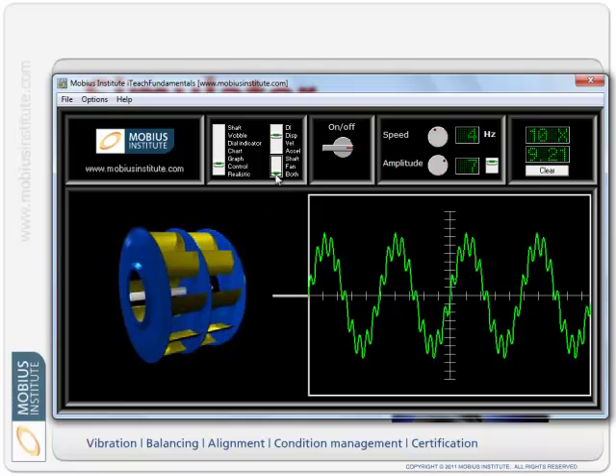And we can demonstrate the two added together. Now I've got the vibration of the shaft, and superimposed on top of that is the vibration due to the fan blades turning and creating pulsations. So there's a lot we can talk about. We can play around with this for quite a while to explain the real fundamentals of the vibration: the addition of two frequencies to each other, and amplitude, and so on.